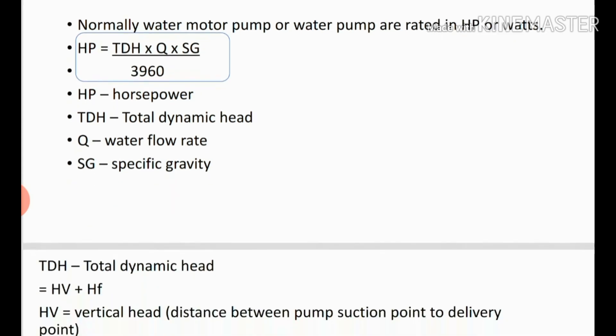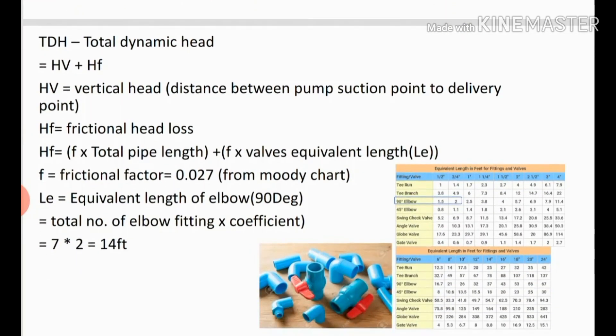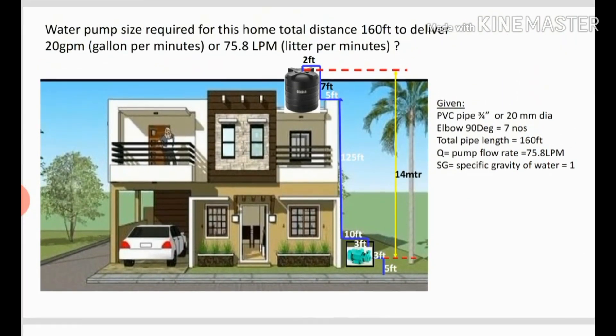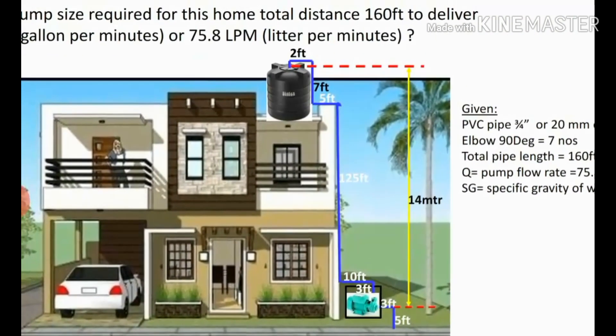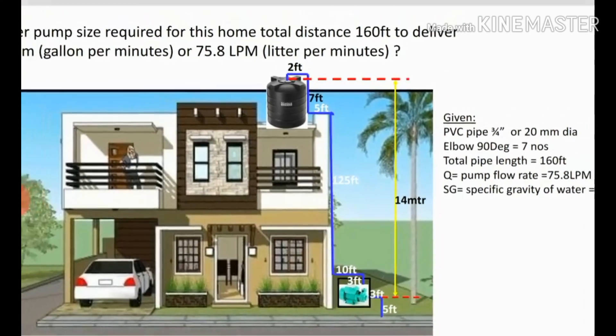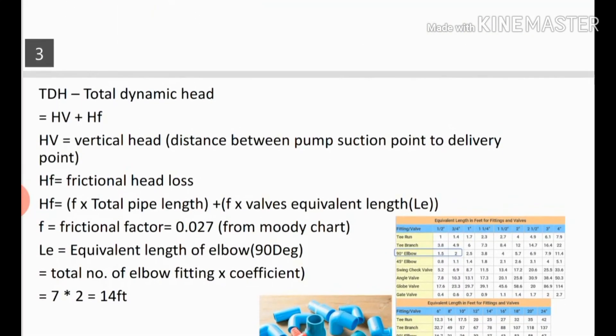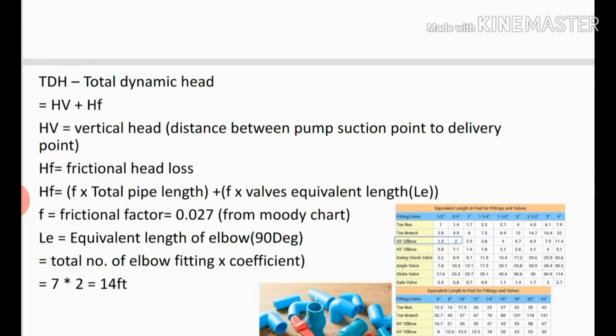TdH stands for total dynamic head. The formula is: TdH = HV + Hf. Here HV means vertical head — that is the distance between the pump suction point and delivery point. From the example, the suction point to delivery point is 14 meters, so we already have the Hp value.